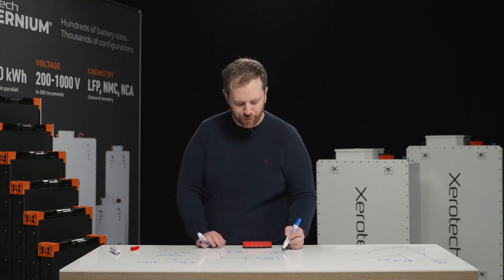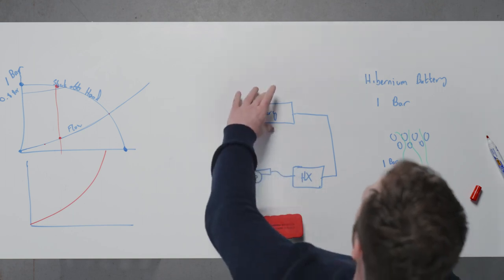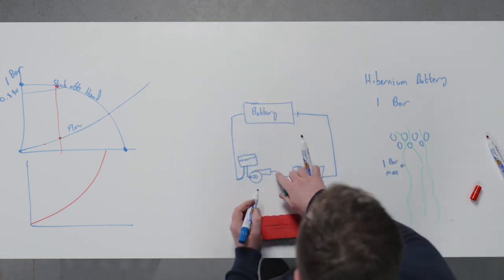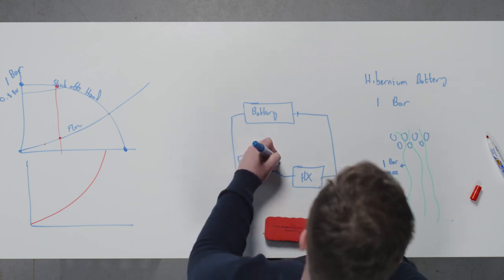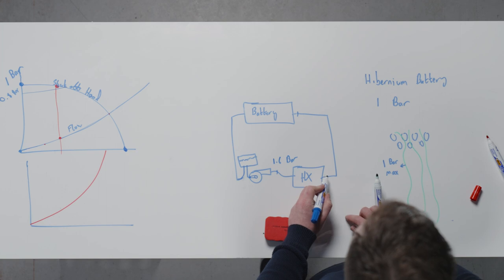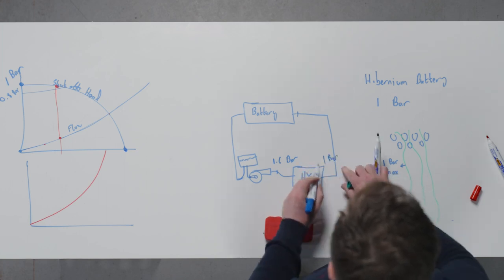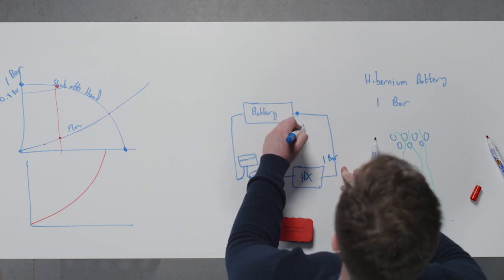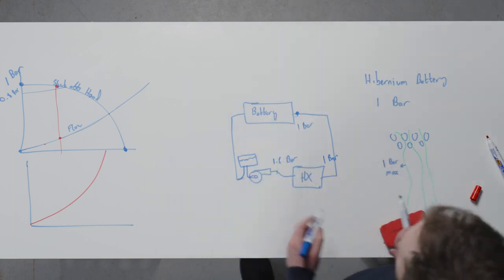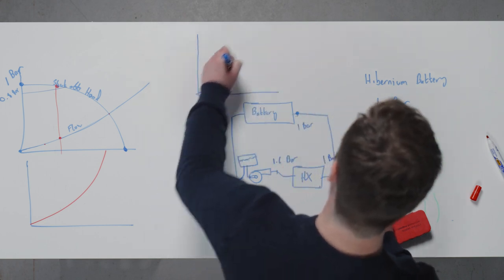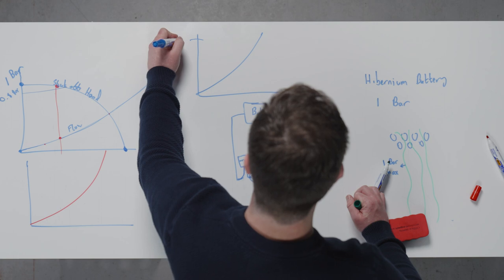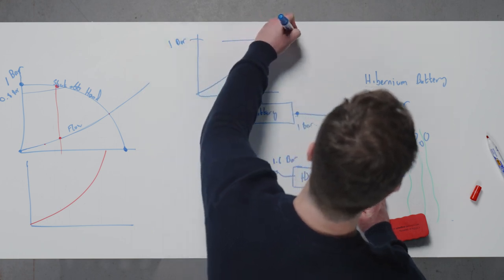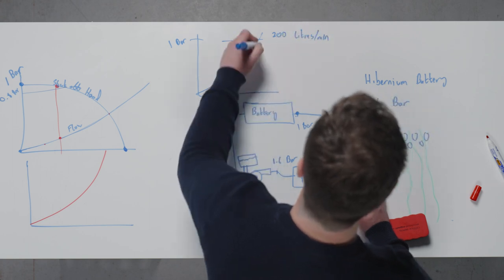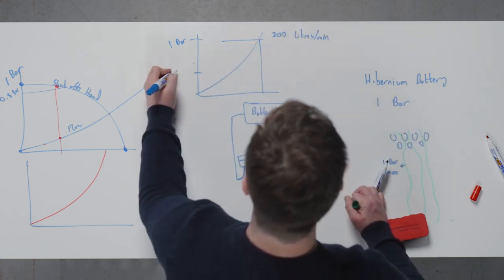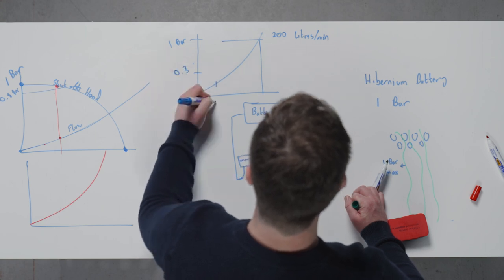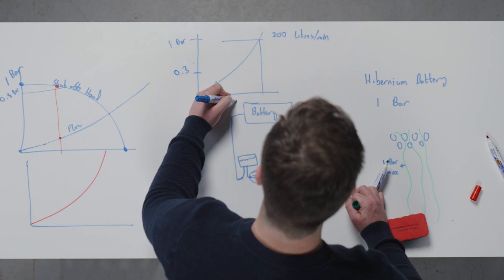But what's important here is if you're trying to develop maximum flow rate, if you put the battery in this location, you can have your pump inlet pressure here being maybe 1.6 bar, and it pressure drops across the heat exchanger, and you've now got 1 bar here. So the battery is experiencing a maximum pressure of 1 bar. And if you were to look at the characteristic curve of our battery with flow rate, it might turn out that 1 bar can equal 200 liters a minute, whereas 0.3 bar might only be 30 liters a minute.